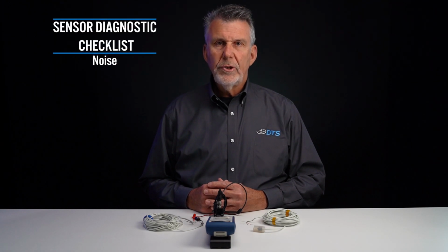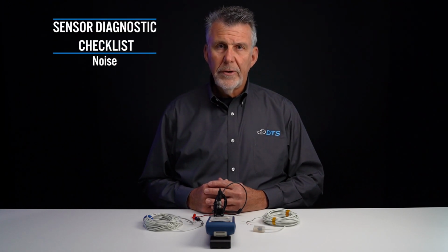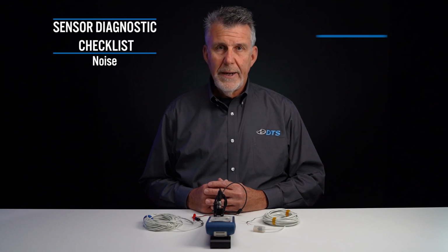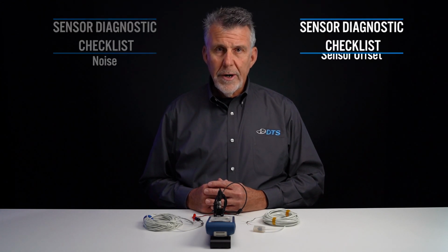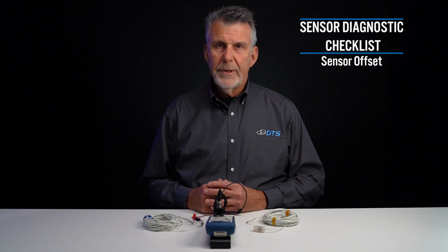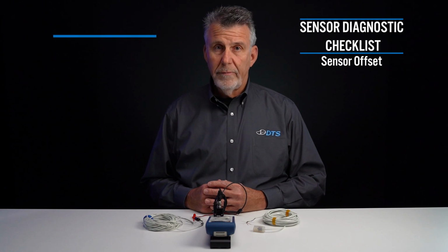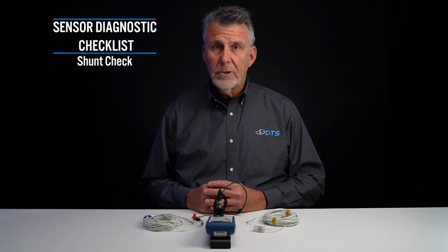Next, we do a noise check, which basically confirms that you've got good cabling and good grounding by indicating a low noise level. Third, we have sensor offset checks. This is a very basic check that indicates whether or not the sensor is functioning in its normal voltage range. And finally, whenever possible, we recommend doing the shunt check feature in the software because this is a cross-check of the gain, the sensor is connected in the proper place, the impedance or the resistance of the bridge is correct, and it really proves that a lot of things are working well.